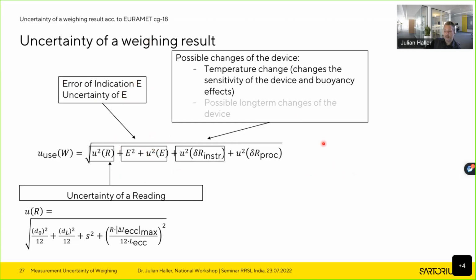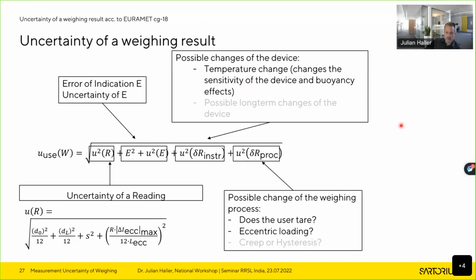And now the next one is that, from the calibration on, of course, possibly the device might change, and especially, of course, due to possible temperature changes. We know that there is usually a remaining temperature sensitivity of the device and also buoyancy. So the air density will change with temperature, and this has to be taken into account. And of course, the user might use the weighing instrument slightly differently than it was used during the calibration. So for example, the user usually might use the tare function, and he might place weights or weighing goods more eccentrically on the weighing instrument. All of that has to be taken into account when stating the uncertainty of any weighing result.